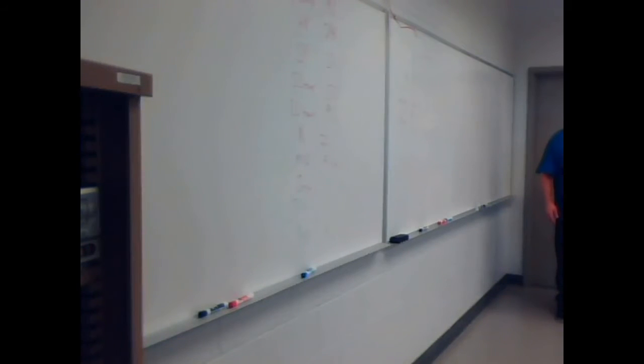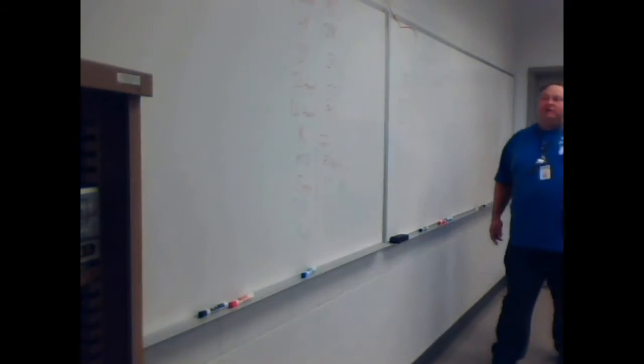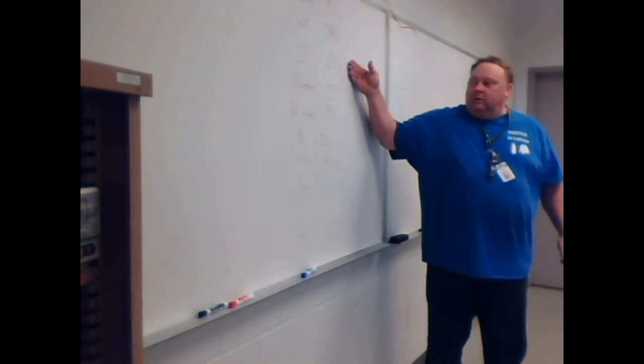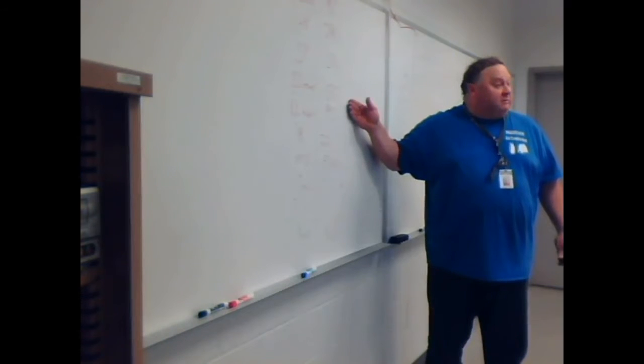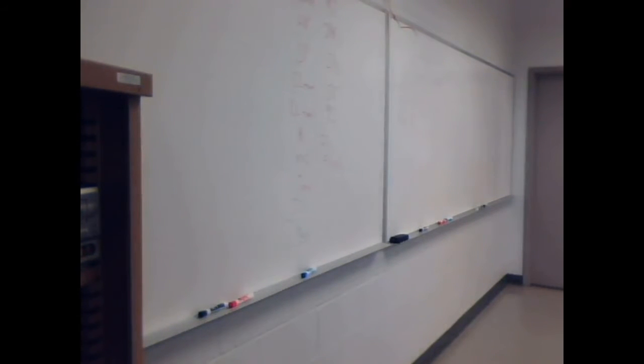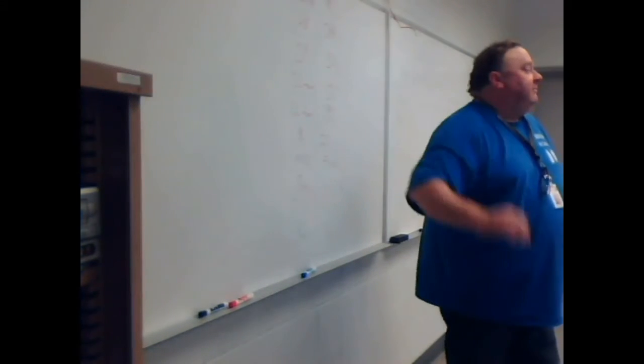I don't understand. This is a pressure. Your gauges gave you a pressure. Well, we have a temperature also. You had to take the temperature also, yes. An actual temperature: you took your meter and hooked a clamp meter on, and it said it was 50 degrees. Everybody in here has a digital thermometer. You put it on something, it'll read the temperature. We did that on the suction line coming out of the air handler.